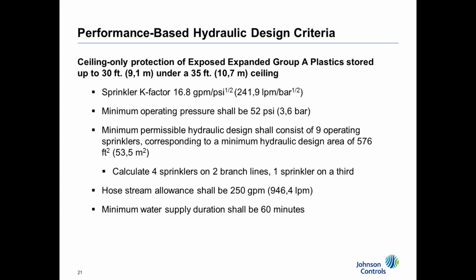What's really interesting is, although we've only tested the 35-foot building with 30 foot of storage, that's for the sprinkler. If you were to take the electronic, because it has a 3-foot tether that runs from the metron to the electronic sensor, there are going to be cases where you may have a 36 or 37 foot tall building, which would still fall inside of this envelope, just because electronics can be placed above where the sprinkler testing was done.